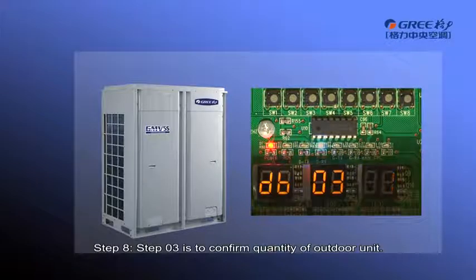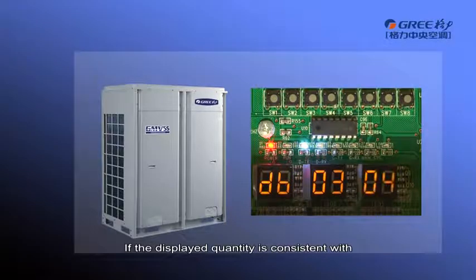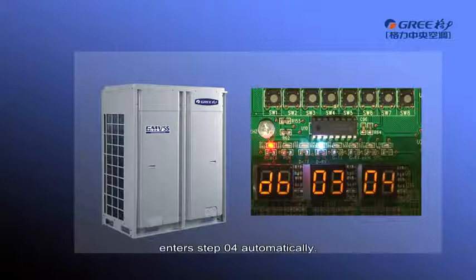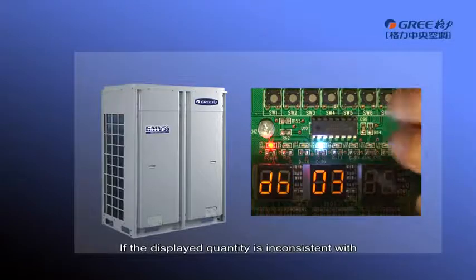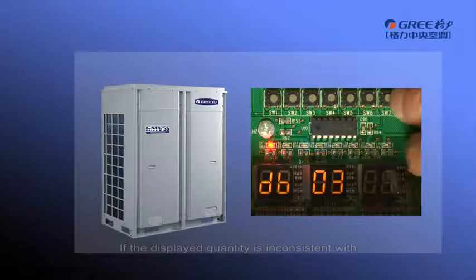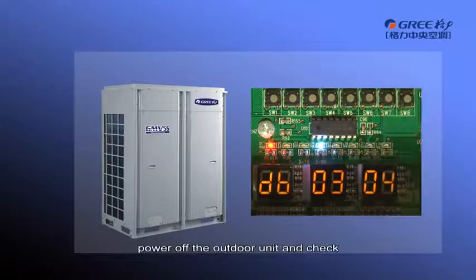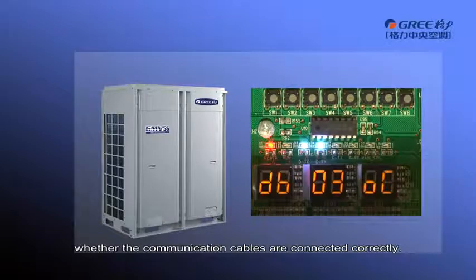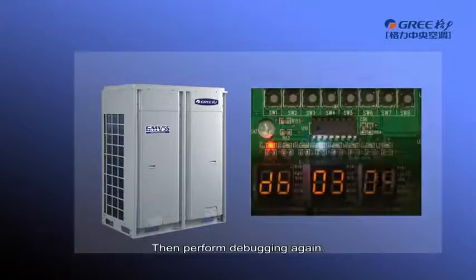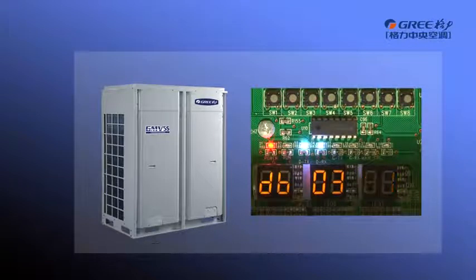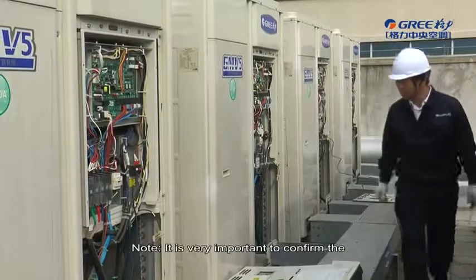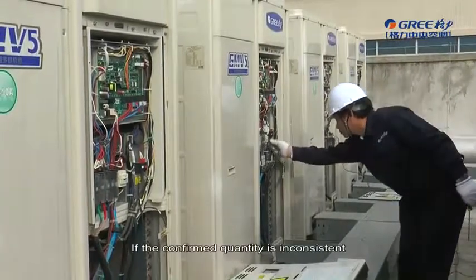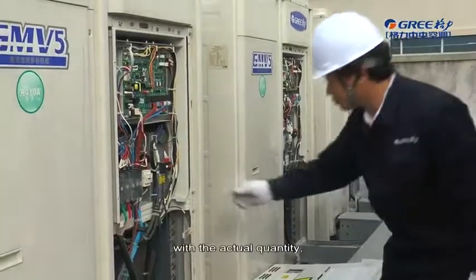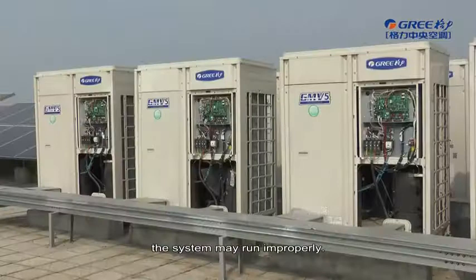Step 8. Step 3 is to confirm quantity of outdoor unit. If the display quantity is consistent with the actually connected units, the unit enters step 4 automatically. If the display quantity is inconsistent with the actually connected unit, power off the outdoor units and check whether the communication cables are connected correctly. Then perform debugging again. Note, it is very important to confirm the quantity of outdoor units. If the confirmed quantity is inconsistent with the actual quantity, the system may run improperly.